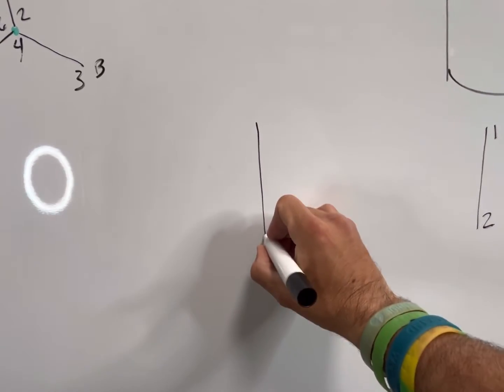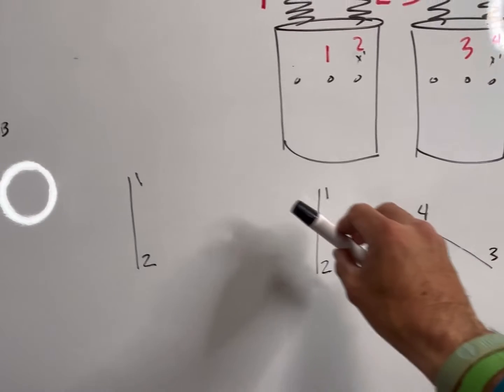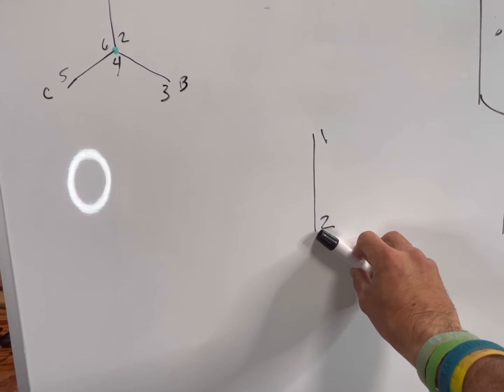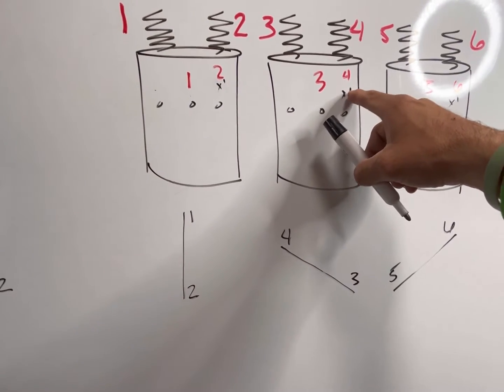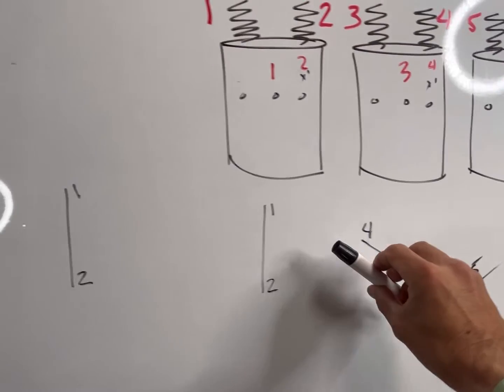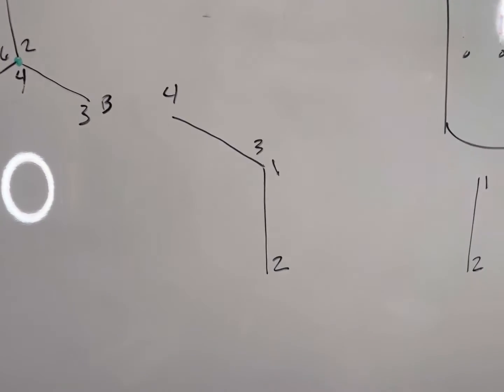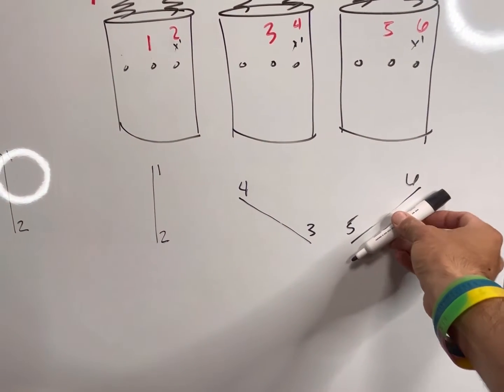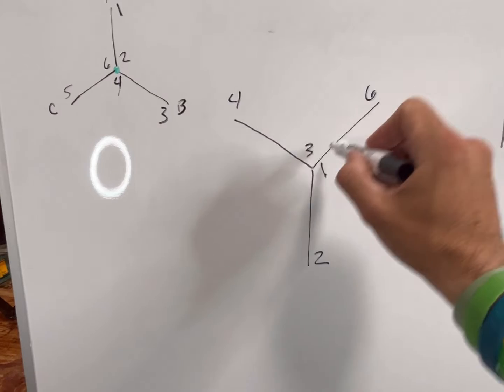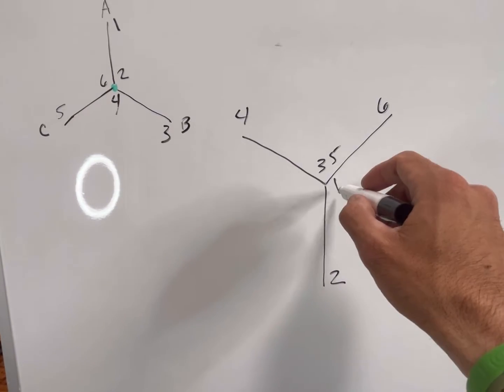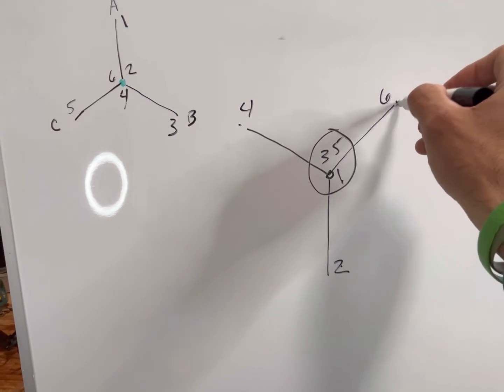When I take these vector angles and start placing them to make my Y shape, I have to consider where X1 is so that 2, 4, and 6 are pointed out toward the phase. I pick up my 3-4 line with 4 on top, and instead of tying 2 and 4 together as common neutral, I make 4 my phase — X1 is my phase. I do the same with 5-6: six on top, five on bottom, making that Y shape. The result: 1, 3, and 5 tied together as common neutral, and 2, 4, and 6 as my respective phases.